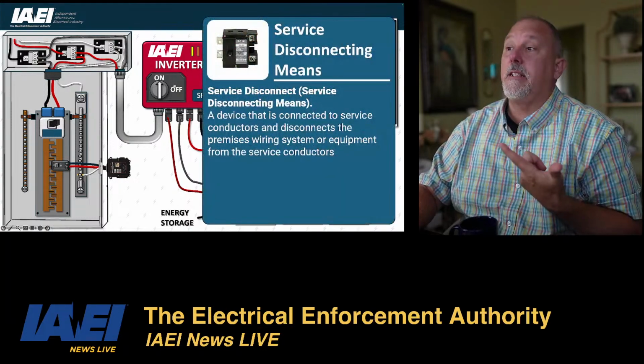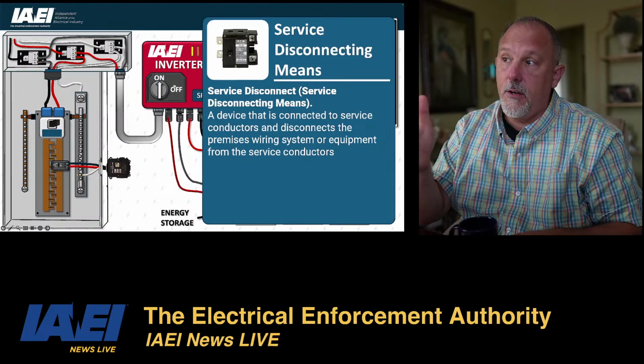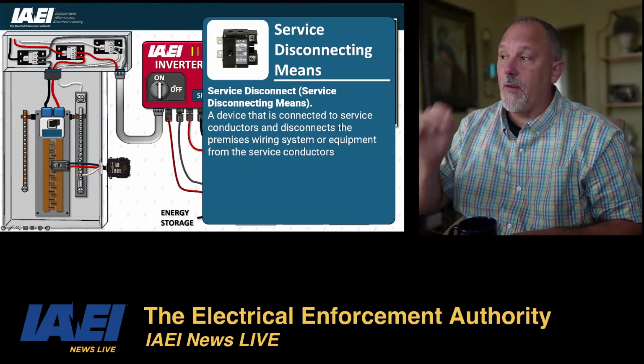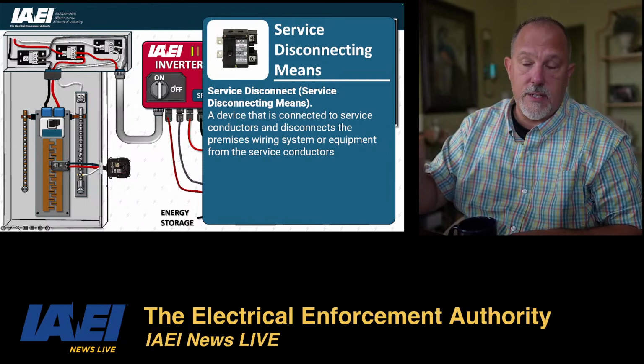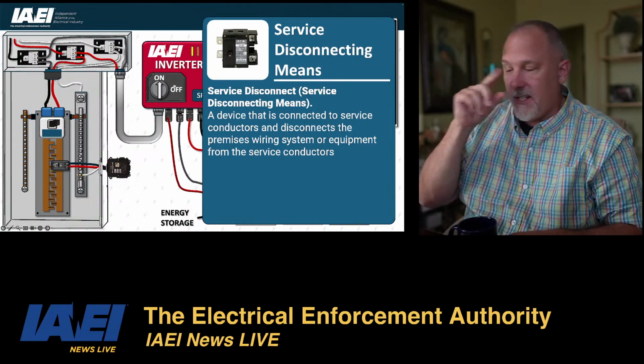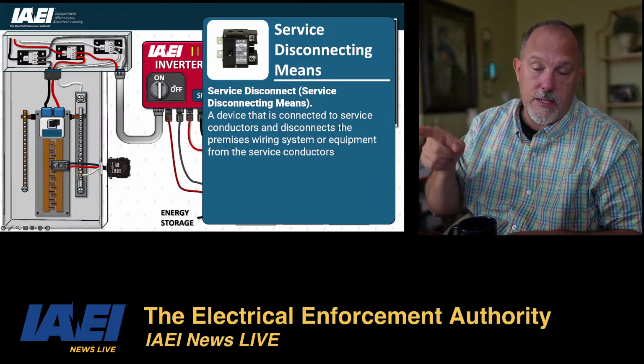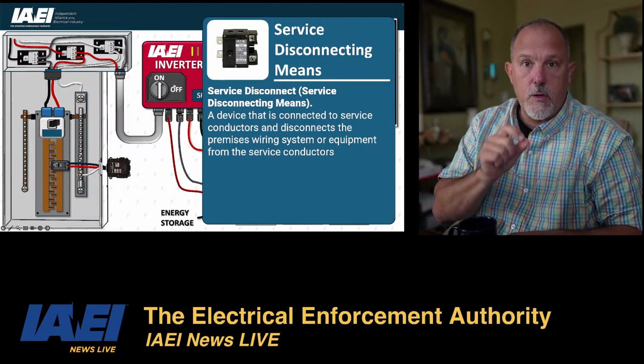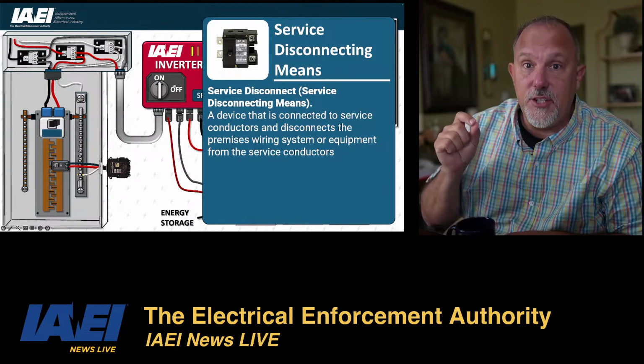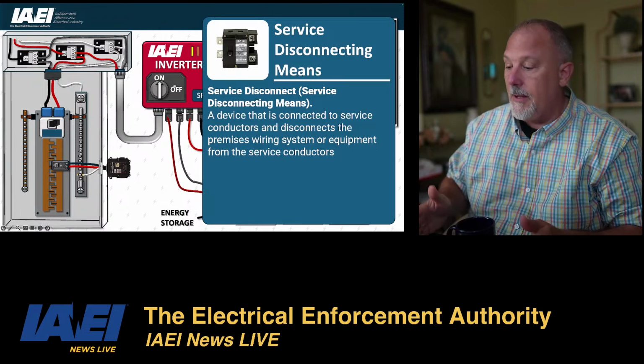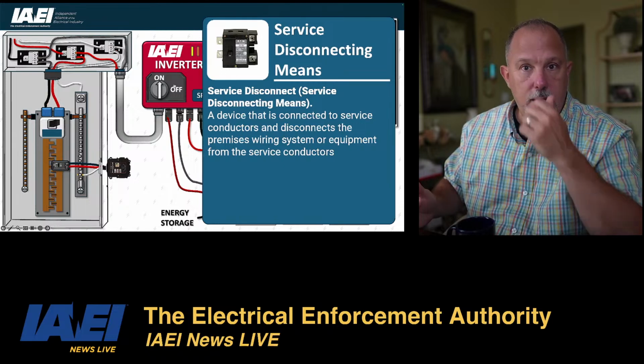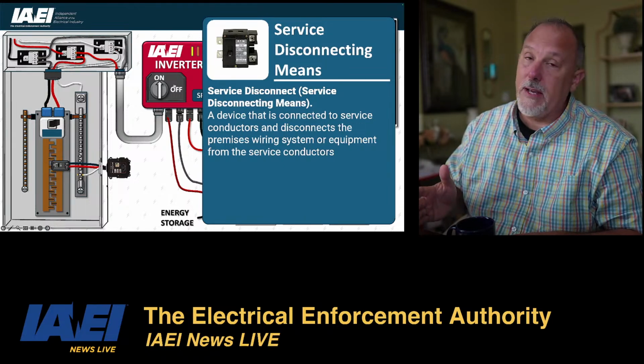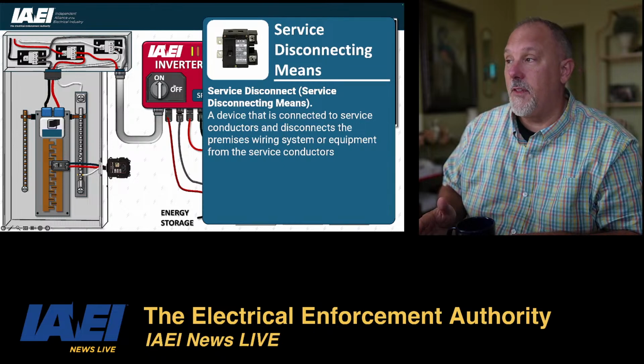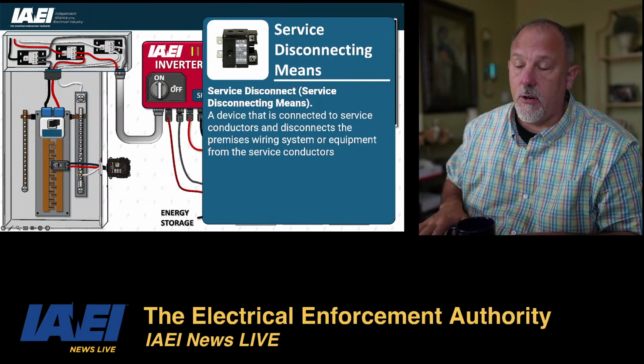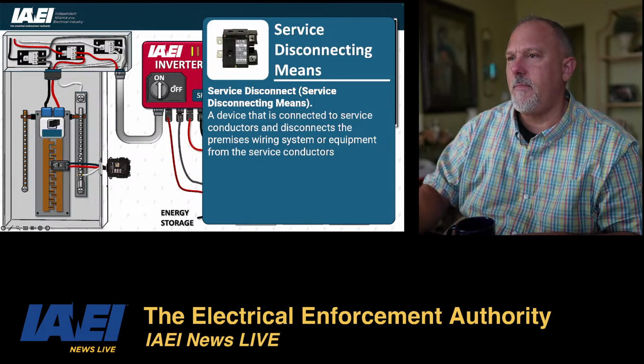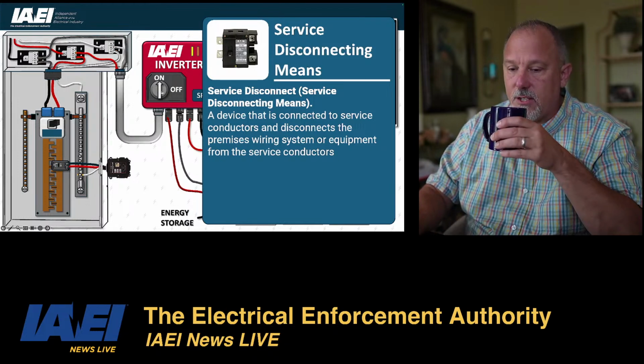This is a service disconnecting means, right? So that disconnect in this inverter, because it is disconnecting you from the service conductors, it is a service disconnecting means. And that definition right there is new for the 2026 code cycle, which is a critical piece. So we now have a defined term, or we will have a defined term if it passes through the second draft. Panel 10 did a lot of work for this defined term, and we made a lot of other changes in Article 230 to accommodate it. So that's a service disconnecting means.